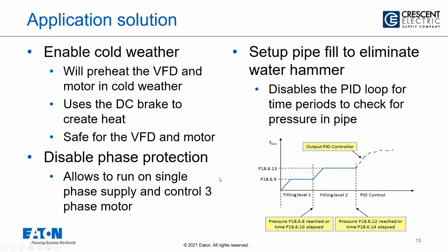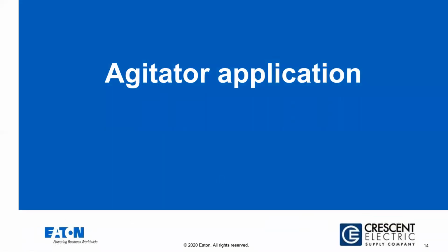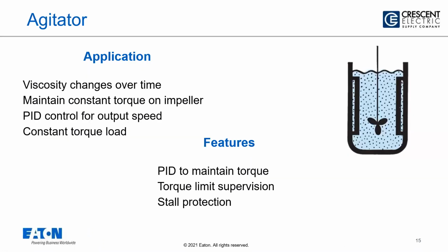Next one, Jerry. Then I'm going to talk to you about the agitator application: agitator, mixer, blender, those types of applications. And this drive, both the DG1s and DM1s, are dual rated. So you can select them for a variable torque application, or you can use the same drive for a constant torque application with 150% overload for a minute and 200% for a couple of seconds. So this is a constant torque application, as mentioned on this slide.